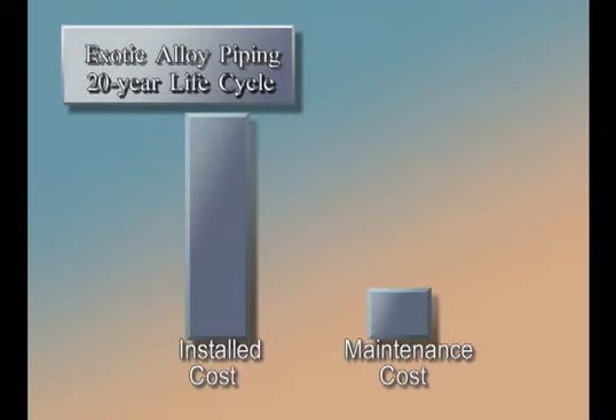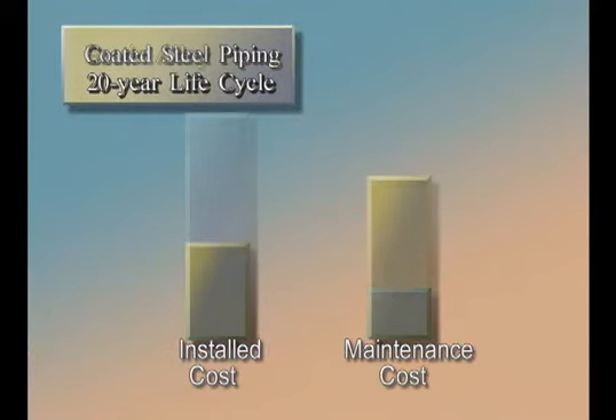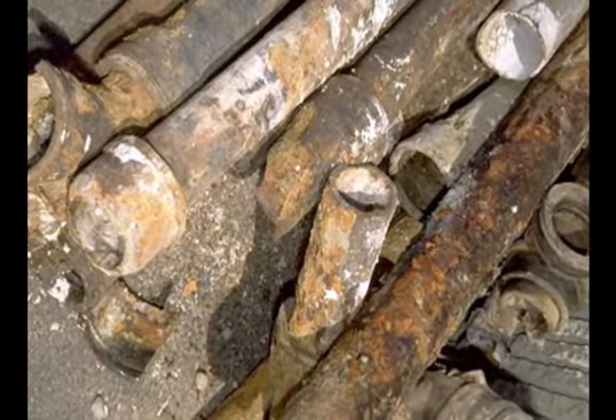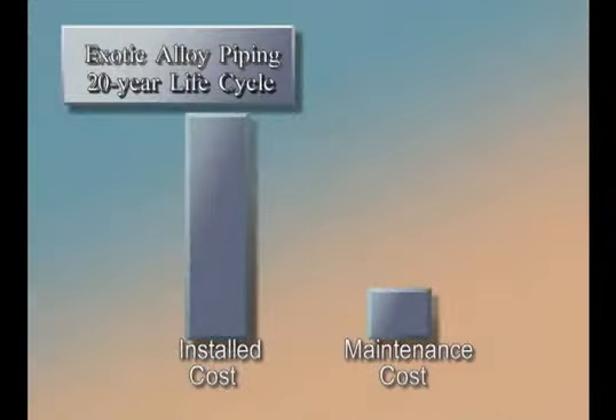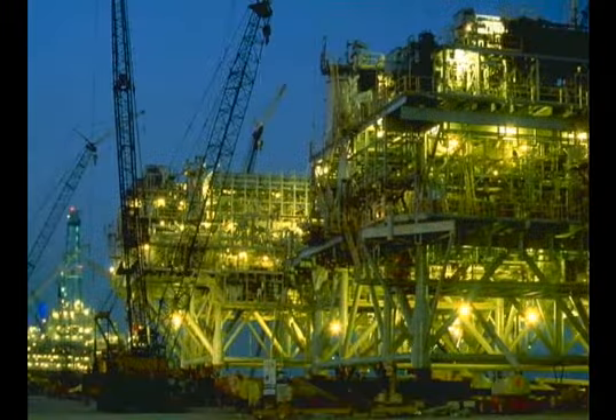Exotic materials like stainless steel or 90/10 copper-nickel piping are less affected by corrosion, but these systems can be 3 to 4 times the cost and may require special welding techniques for installation. Coated steel pipe only partially solves corrosion issues, since joints, fittings, and flanges present numerous sites for potential discontinuities in the coating and subsequent corrosion. Considering its life cycle cost, metallic piping has proven to be costly for saltwater systems. When coupled with the safety issue of internal corrosion, the use of metallic piping in critical fire safety systems seems to deserve some rethinking.